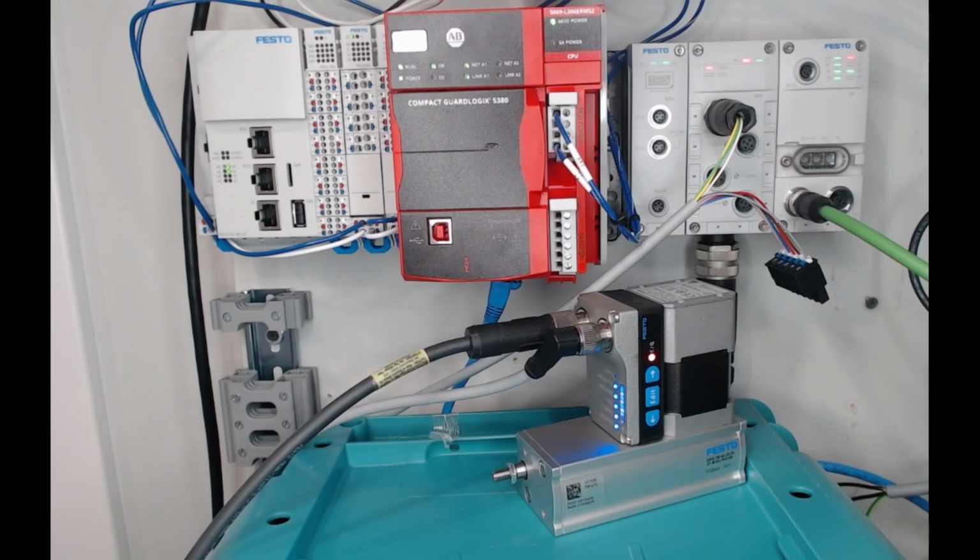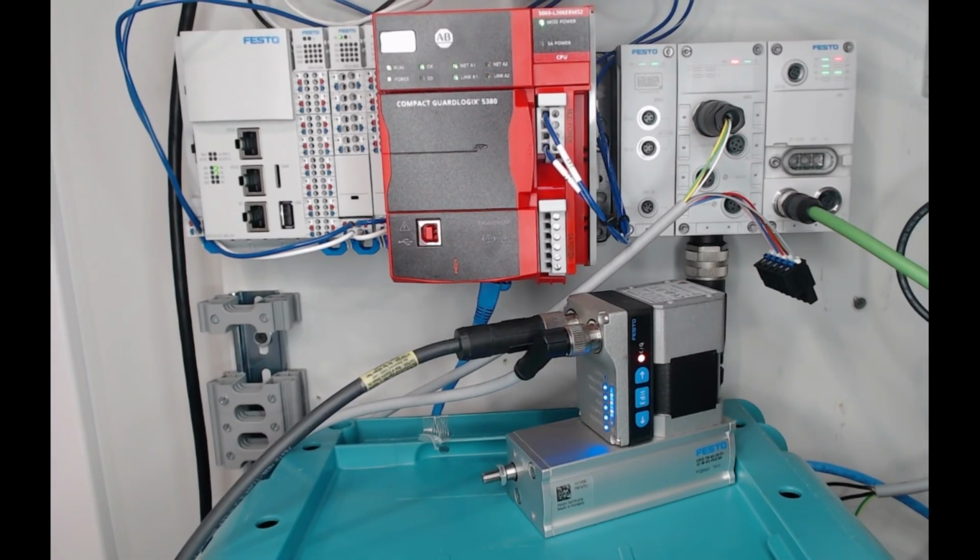linear motion, it requires a home move on the first power up. So for these motors, if you tell it to initially move out, it's going to perform a home move where it moves to the in position and then it will move out. And this kind of unwanted motion can be unexpected and possibly cause damage to your system. So to overcome this, we have a new startup AOI, which will perform this home move and also clear any recoverable errors so that when the done bit goes high, you can then move forward with any normal operation.